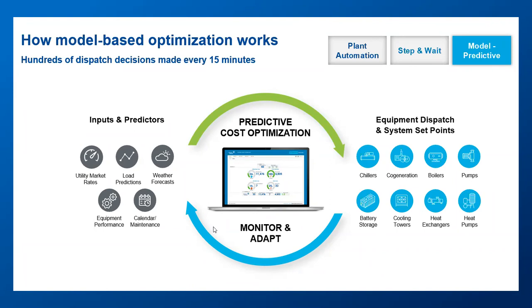The benefit is that rather than having static rules programmed into a controller sequence, this process is more of a cycle, because the models and algorithms can adapt and learn over time as conditions change. For example, if a chiller's tubes are slowly fouling over time, the system may understand that the part-load efficiency curve of that particular chiller has changed relative to the others, and so it may choose a different chiller to run as a result, and alert the user to a possible maintenance opportunity as part of a fault detection recommendation.